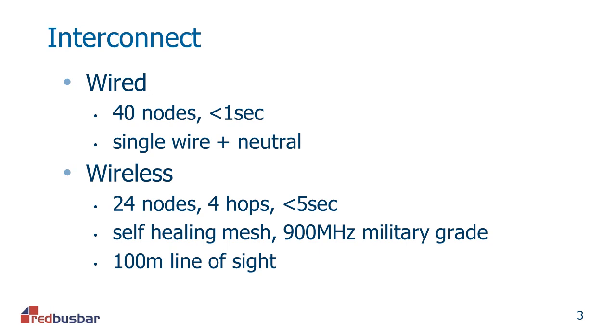So it extends the robustness of the network. It's a self-healing mesh, and what that means is that if one of the nodes on the network fails, the message will be routed via a different path to achieve communication to all the nodes. It's a 900 megahertz military grade network, so in that respect, it's very robust and well understood for its integrity. Smoke alarm communication is 100 meters line of sight, which is an unusual specification because you very rarely have that. You can relate that to an actual building, but we haven't had a circumstance yet with buildings whereby the radio signal hasn't been able to pass through reinforced concrete floors and walls.